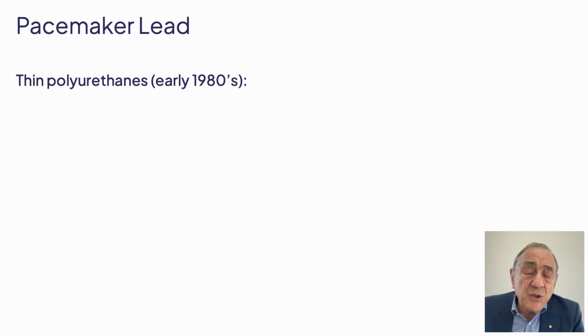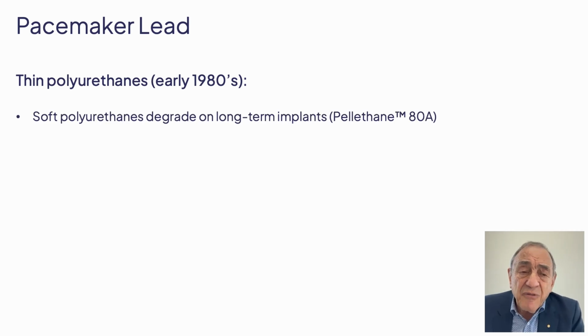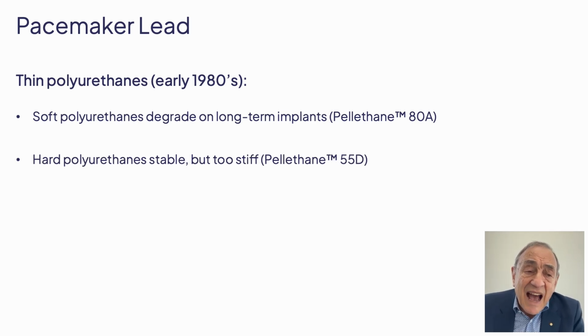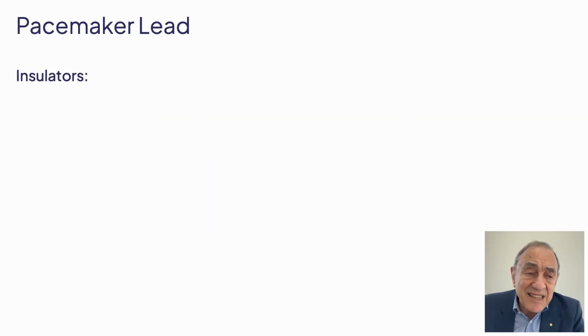Thin polyurethane leads were introduced in the early 1980s and completely revolutionised pacemaker leads. However, after a few years, it was recognised that the popular soft polyurethanes degrade after 2 to 3 years of implantation, and hundreds of thousands of leads required replacement because of this. There was a hard polyurethane lead, which was much more stable, but too stiff and caused perforations. So both polyurethanes were not suitable for the pacemaker industry as such.